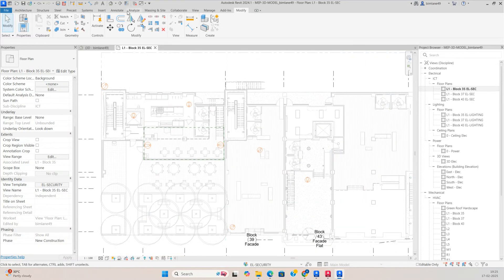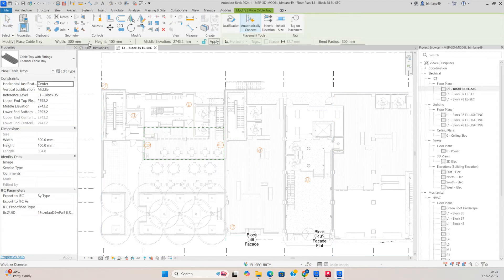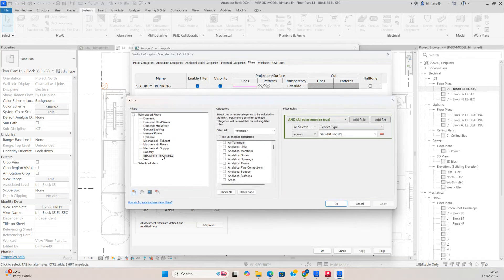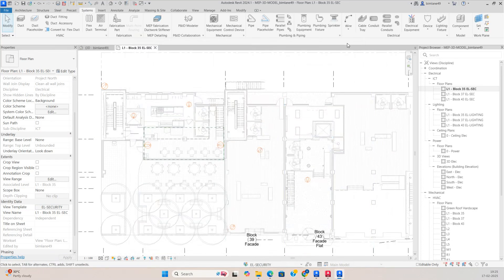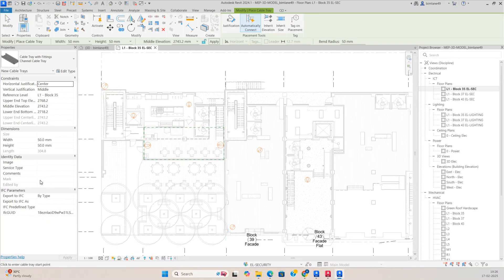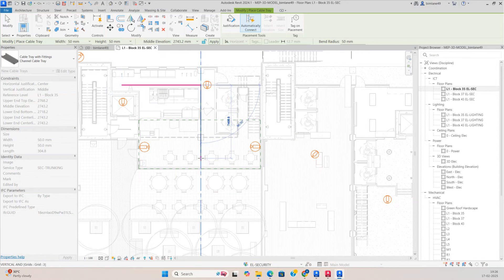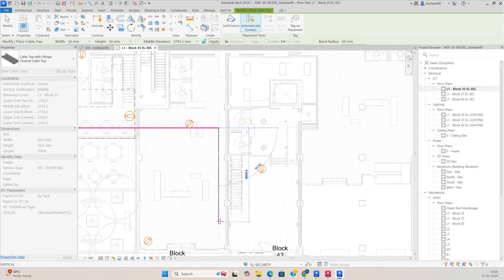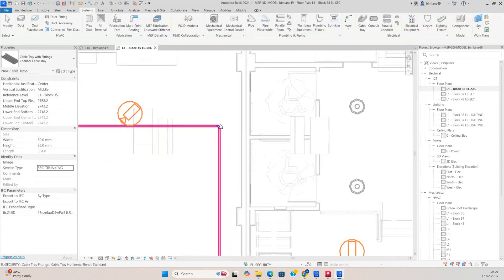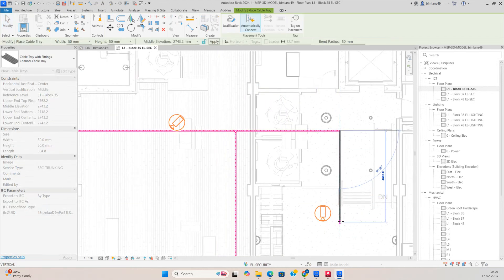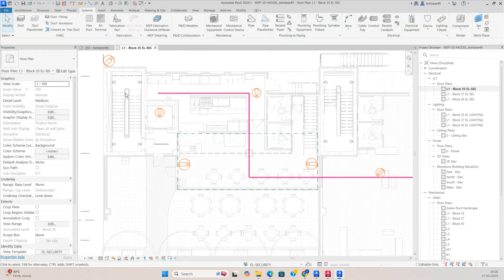Go to the System tab and make a cable trunking — for example, 50 x 50. Then give the Service Type as 'Security Trunking', matching the filter you created. Copy that text and make the trunking from here — 50 x 50, service type Security Trunking. Wherever you require the trunking, you can make it like this. In this portion also you need to make trunking, so make the cable tray and connect it to this one.